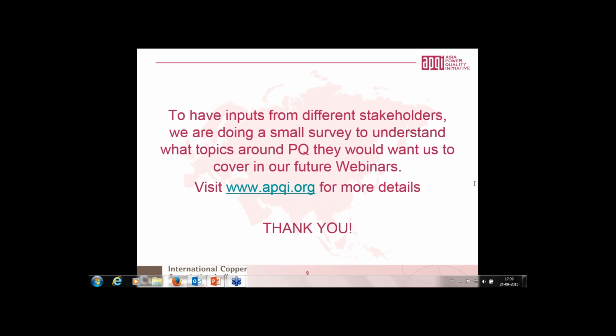What Mr. Sanjeev said is very correct, downstream is a very simple way to know whether the problem is at customer end. Probably we also need to check the performance class of the meters which are there, because current issues will always be at the customer side. If there are voltage issues and no significant events recorded at the grid level, it means they were so subtransient that the protection relays have not got triggered. There could be a performance class of meter problem. Ours are class A meters, and sometimes switching surges may have resulted into this, but since it is not classified as tripping in a major grid, it is very difficult to identify such events.